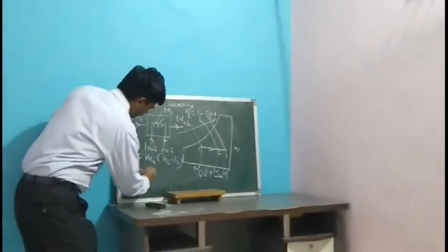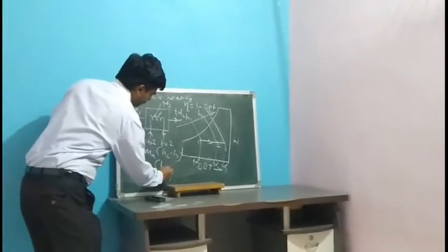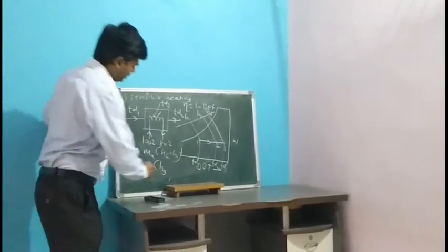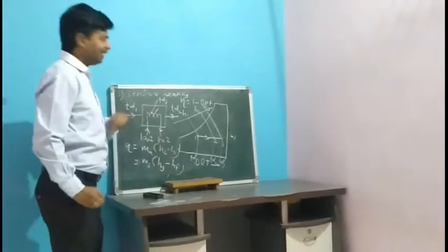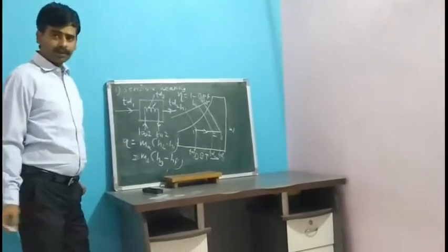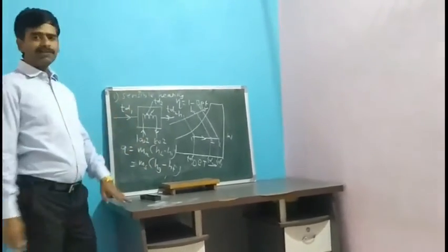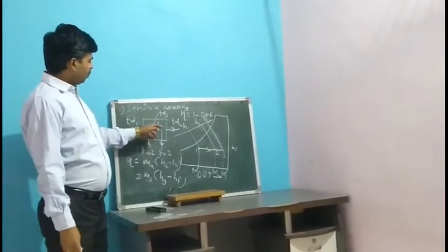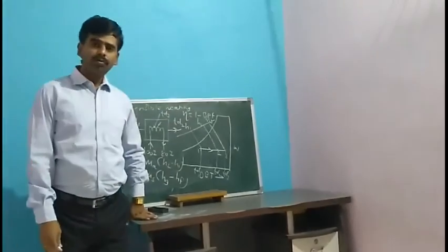So it is the mass flow rate of that steam multiplied by Hg, the enthalpy of the saturated steam, minus the enthalpy of the condensate at 80 degrees Celsius. If you balance this equation, we can determine the mass flow rate of steam needed to flow through the heating coil in order to raise the temperature from TD1 to TD2.